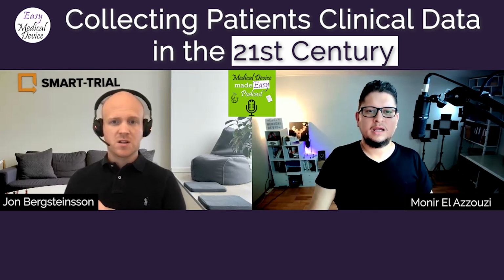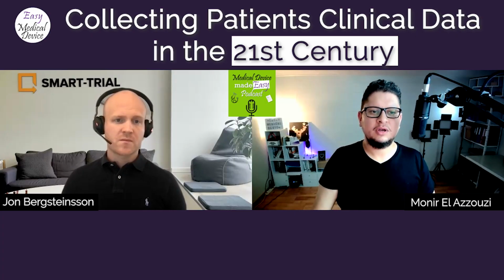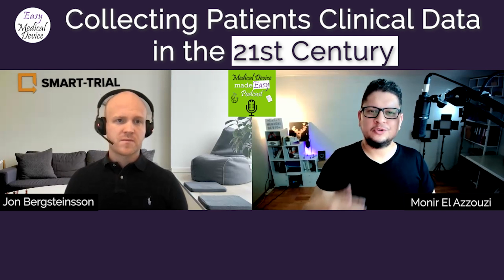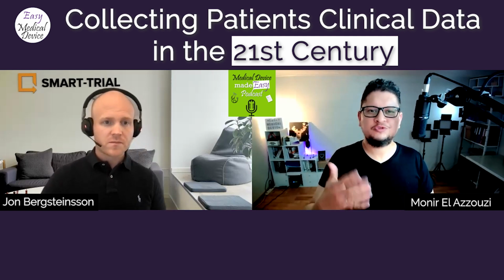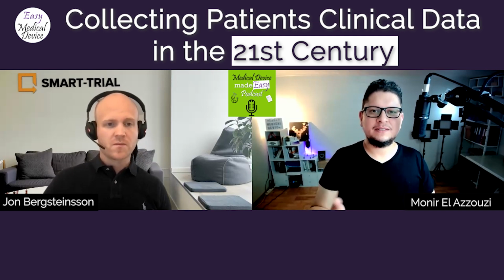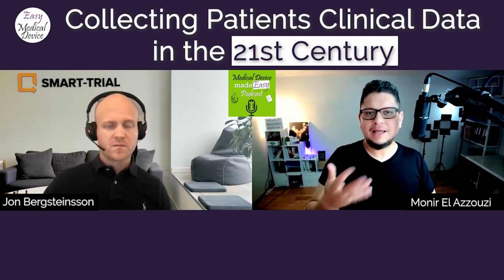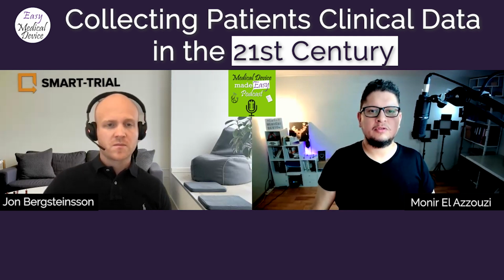Yeah, I think it's important to understand that when you do a PMCF, so a post-market clinical follow-up, you have to use the device as it is described on the CE certificate. So you should not create a new intended purpose or new features or whatever. It's just to verify, as you've said, the efficiency and the safety of the device as you got the approval for it on the market. So there is no change.